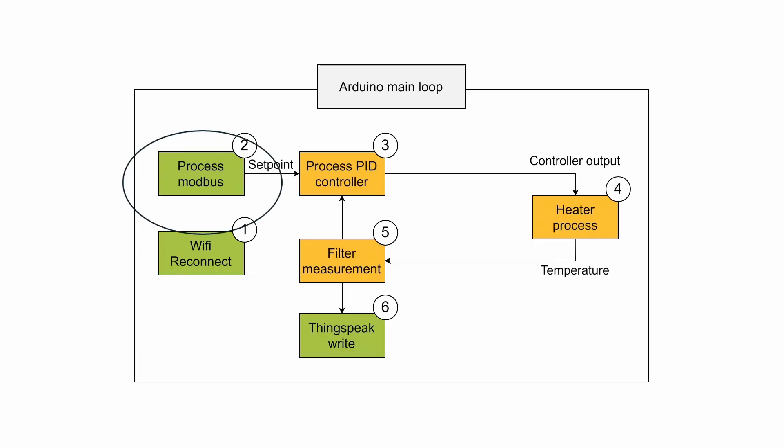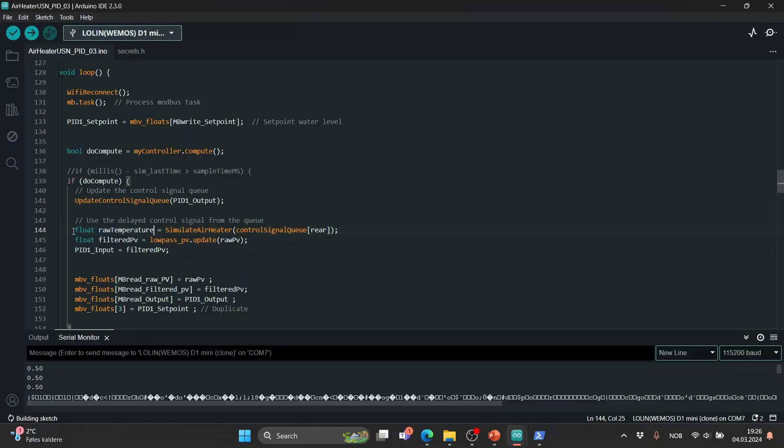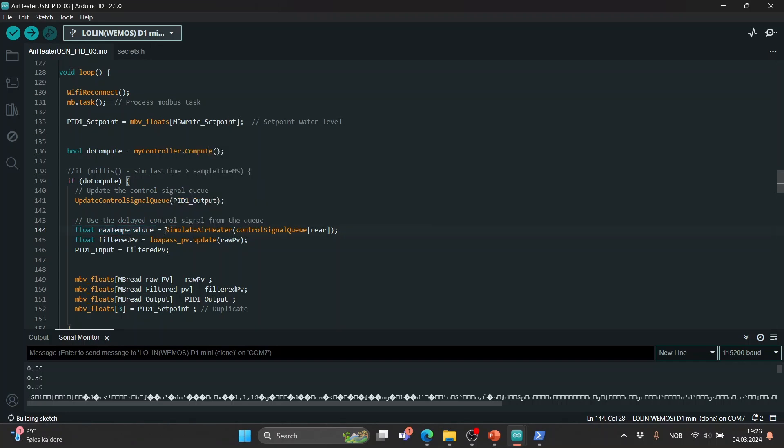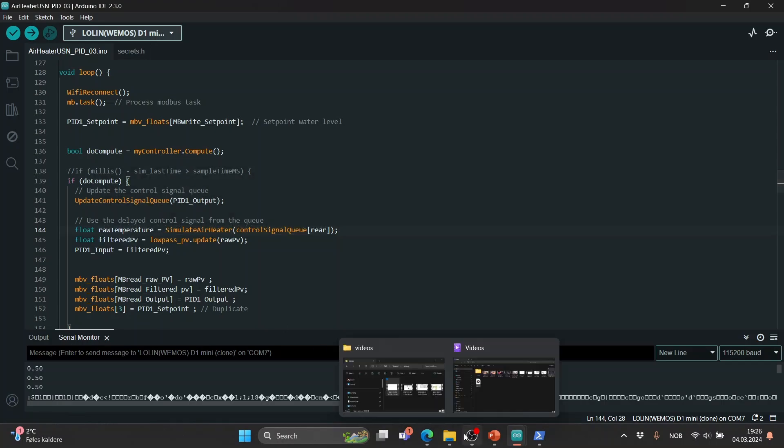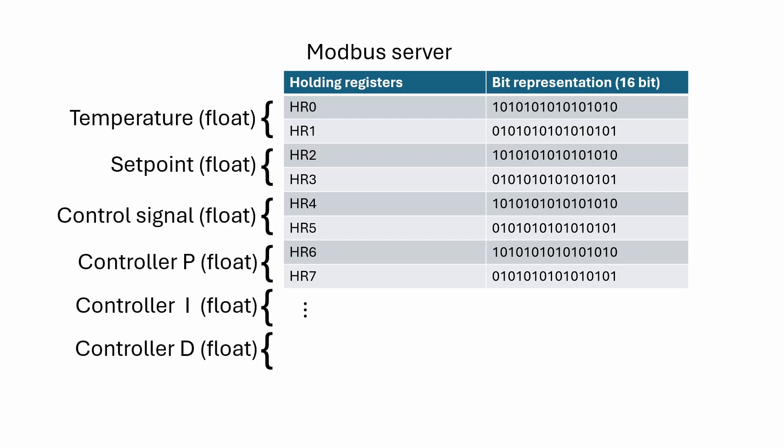When Modbus is handled the processor must respond to either write or read requests from the outside world. The requests can only interact with a set of 16-bit values called holding registers. This is often defined as an array in the code and it's here we will put the values we want to transfer. The values in my code is usually of the data type float. One problem that occurs here is that the float variable type uses 32-bit for storing its value under the hood and in a normal holding register there's only 16-bit. Because of that we need to use two holding registers to store this value. And we do it this way with all the variables.